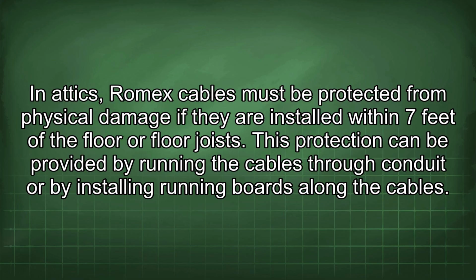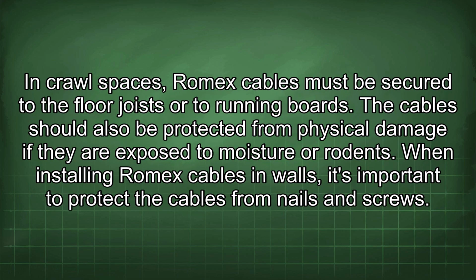In attics, Romex cables must be protected from physical damage if they are installed within 7 feet of the floor or floor joists. This protection can be provided by running the cables through conduit or by installing running boards along the cables. In crawl spaces, Romex cables must be secured to the floor joists or to running boards. The cable should also be protected from physical damage if they are exposed to moisture or rodents.